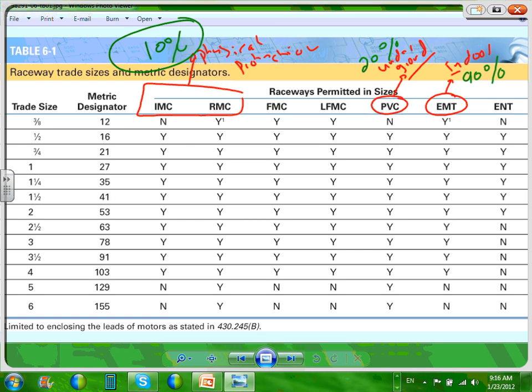We'll talk about it. Rigid is the largest, and there's three actually differences. The thickness of the wall, the rigid is more thick. They manufacture them in so many materials too. You can get steel, aluminum, brass, red brass, rigid. So they make them in so many materials, rigid, versus IMC, which is limited to steel. Any question, guys, about these before I go to the last, flexible metallic conduit?